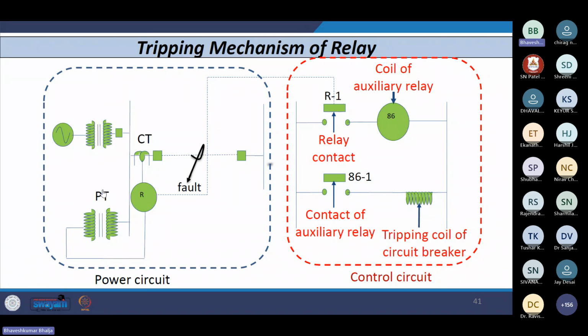So now what is the advantage? We reclose, and this is done automatically, right? Manually it is not possible because you have to reclose it in 300 milliseconds, 0.3 second. So this is done automatically using a sequence, known as the auto reclosing sequence. Now, why is this required? If a fault occurs and you have opened the breaker, and it is transient in nature, it is going to die out. 300 milliseconds divided by 20 milliseconds gives 15 electrical cycles. Most transient faults are removed automatically by then. They die out. So once you reclose after 0.3 second, your system is healthy.